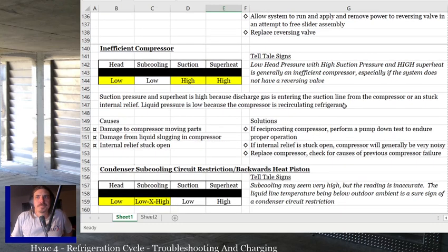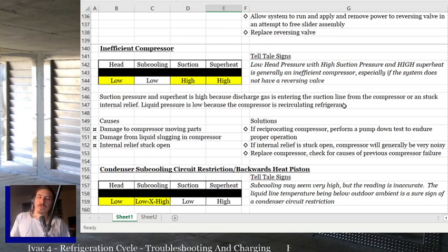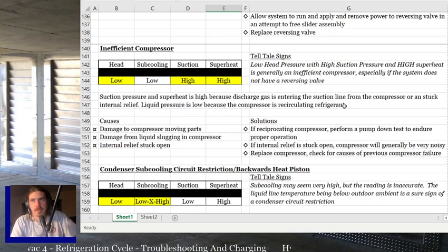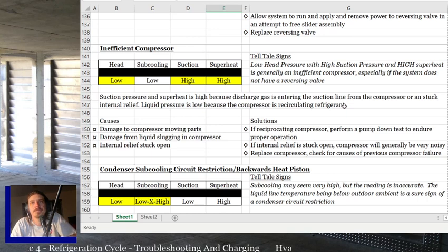Inefficient compressor is the next thing that'll cause that problem. So if you've got the same issues, low head pressure with a high suction and a high superheat, but you don't have a reversing valve, or you have ruled out the reversing valve, then it is an inefficient compressor. And it can still happen with scrolls, and we'll talk about that when we get there. But anyway, telltale signs are low head pressure and high suction pressure with high superheat, which is generally an inefficient compressor, especially if the system does not have a reversing valve or you've eliminated the reversing valve.